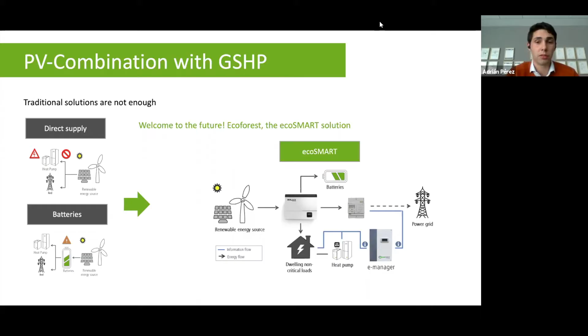For that reason, we are betting on another solution: thermal storage. We developed a controller called EcoSmart eManager that combines the heat pump with other renewable energy sources. The eManager is connected to the heat pump and to the installation's meter through a communication bus cable. When there is a surplus of energy from the PV installation, it tells the heat pump it can use that energy. So instead of using 1 kilowatt per kilowatt, we multiply it by 3, 4, or 5, depending on the COP of the heat pump at that moment.